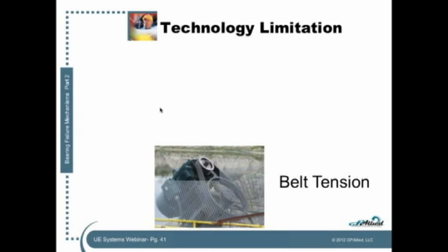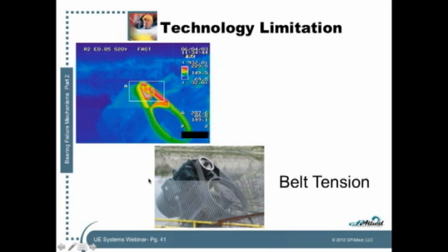Belt tension issue. When we think about these technologies, we need to remember that all technologies have some limitations. Maintenance had just repaired something here. There was a brand new motor, and they called the condition monitoring guys. The vibration guy got there first and said, "Hey, everything looks great. No need for the thermography guy to check it." The thermography guy says, "Well, I drove all the way out here. I'll go ahead and check it anyway."